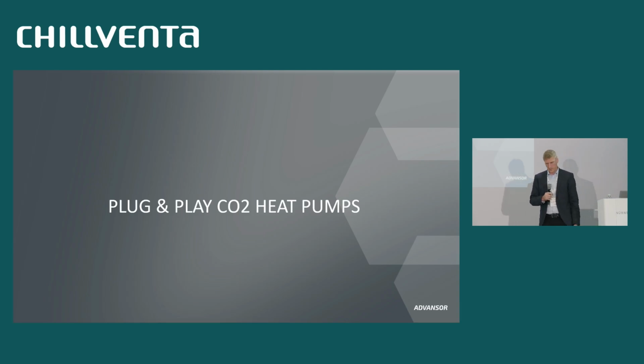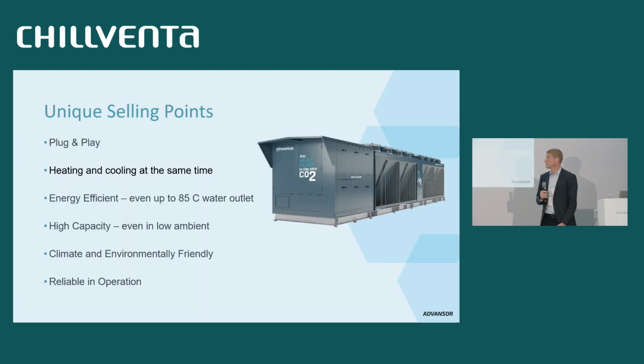Moving to the product itself, the plug-and-play CO2 heat pump. It's plug-and-play, so everything is connected. Everything is finished. It's produced from factory. We can provide heating and cooling at the same time. We have high energy efficiency. We can provide up to 85, 90 degrees supply temperature. And we have high capacity even in low ambient, so this heat pump can operate at minus 20 degrees ambient temperature. Then it's climate and environmentally friendly, as we use CO2 as a refrigerant. So no F-gases, no PFAS, none of that. It's a natural refrigerant. And then we are reliable in operation.